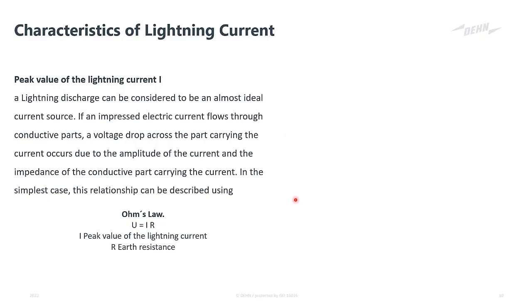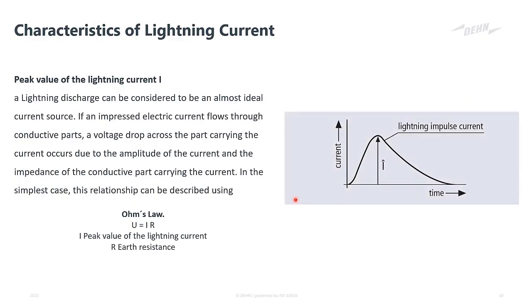As I mentioned, lightning current is an impulse, so it has a rate of rise and then it decays back to zero. Now, we speak about the 10 by 350 microsecond wave shape, where it will reach its peak value in 10 microseconds and decay to half of its value in 350 microseconds. So lightning is very different to something like power frequency, as it's not a sine wave, it is an impulse.